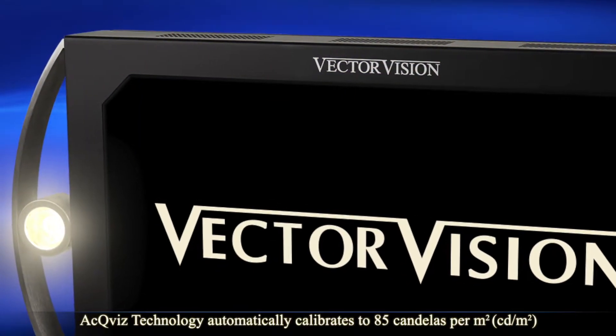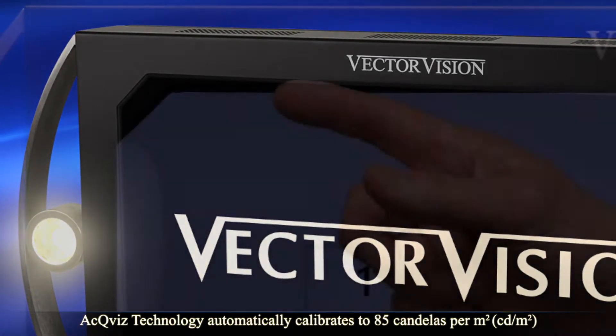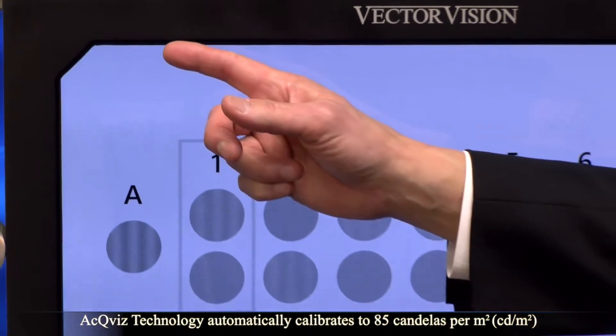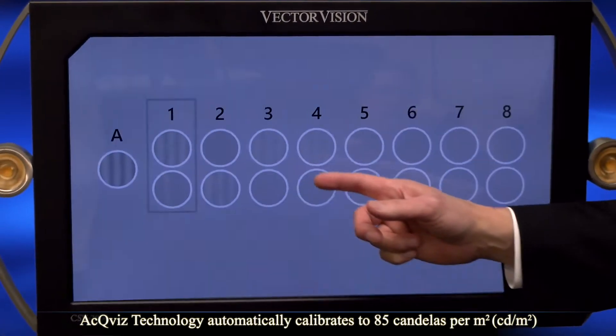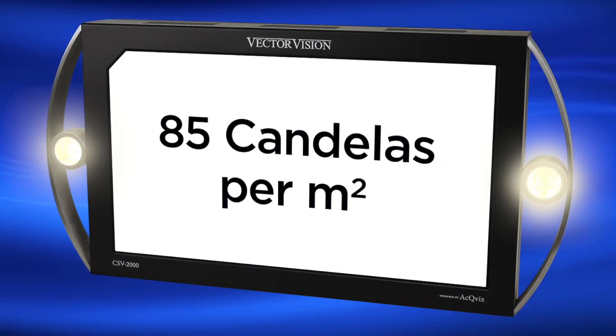The CSV-2000 standardization is powered by a newly patented technology called AcQviz. As you can see, the instrument is calibrating now. AcQviz automatically calibrates the device when it's not in use to ensure a standardized vision testing light level of 85 candelas per meter squared.